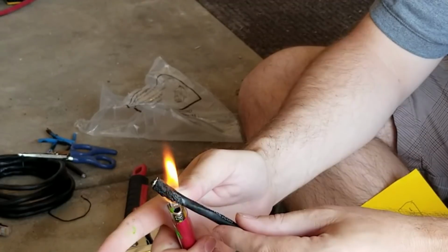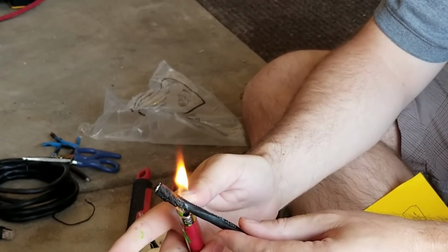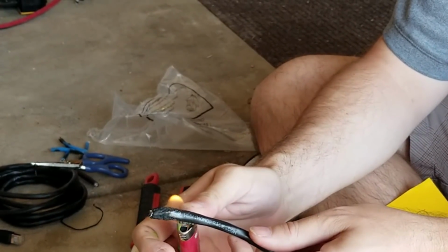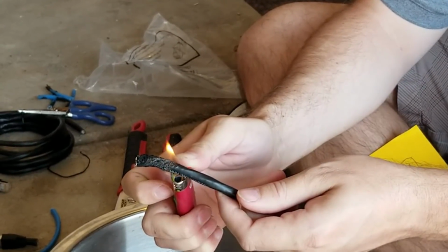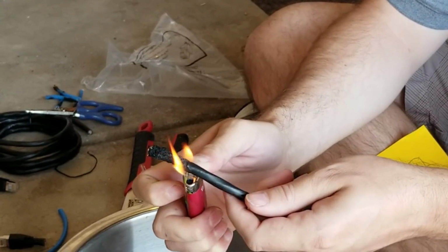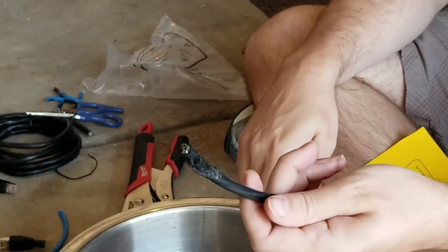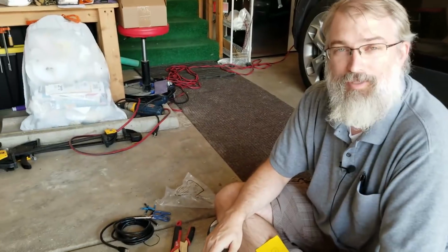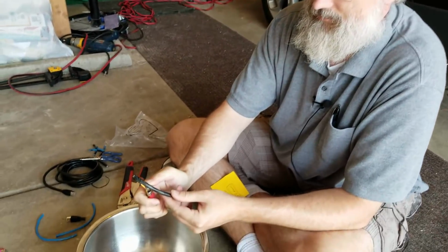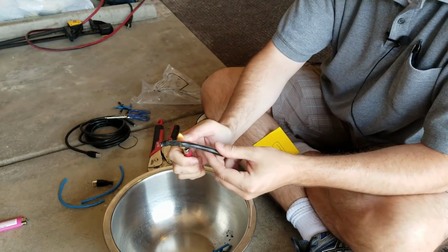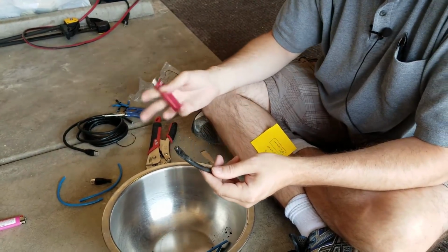You know, there's a little bit of smoke coming off there, but no, that, yeah. Okay. So there is a plenum cable. And it's not nearly putting off. It is definitely a lot less flammable. So there's the difference between plenum and non-plenum. It's just the fact that it's got this coating that makes it fire retardant, and it puts off less smoke, or less noxious smoke, I guess, as it goes. And you have to use it by regulation when you run it through plenum spaces.